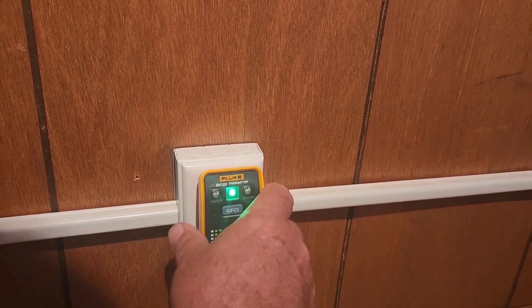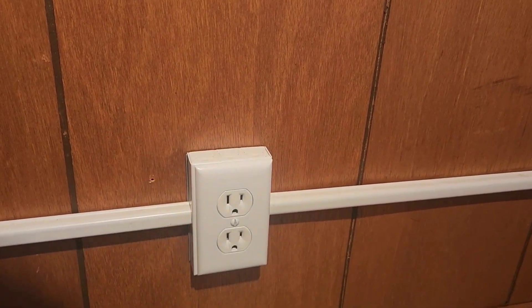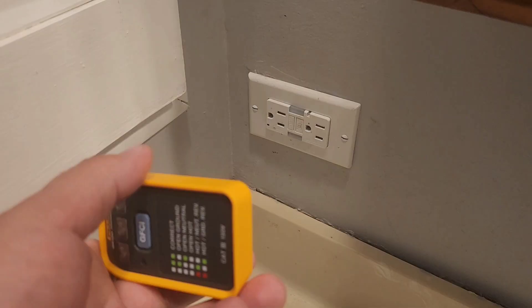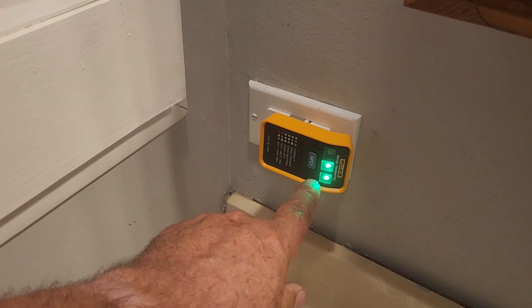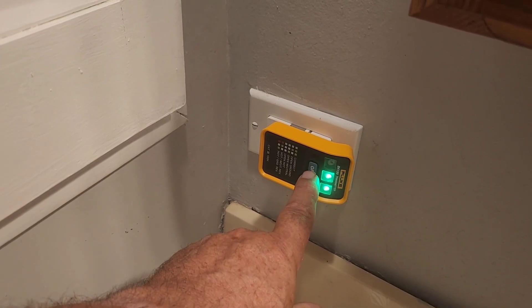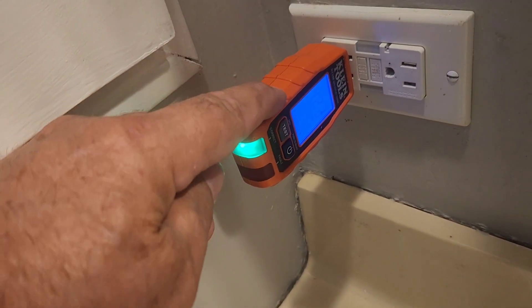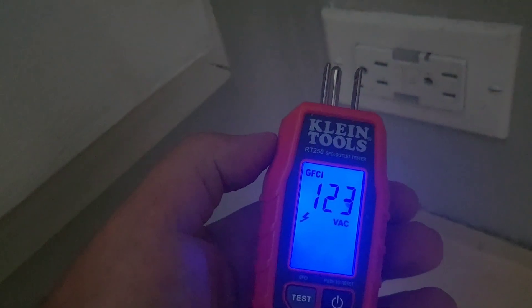One thing about the Fluke: when you unplug it, it doesn't hold the reading. The Kaiweets and the Klein do hold that reading. On this GFCI plug we'll try out the Fluke — plugging it in shows it's wired properly. Hit the GFCI test button — it trips the breaker on this GFCI but doesn't show you anything. Let's reset it and try the Klein — the Klein shows you the voltage and actually shows you how long it took to trip.